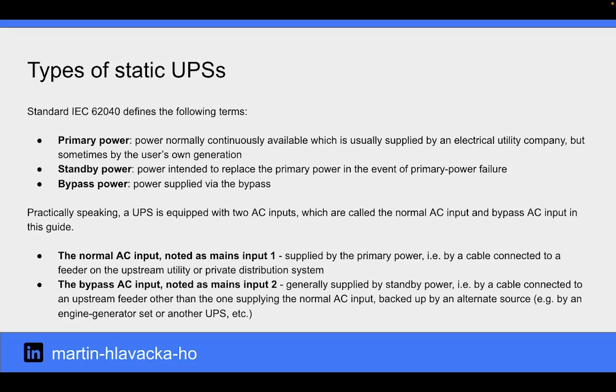Standard IEC 62040 defines the following terms: primary power, which is power normally continuously available that is usually supplied by an electrical utility company but sometimes by the user's generation; standby power, which is power intended to replace the primary power in the event of primary power failure; and bypass power, which is power supplied via the bypass.